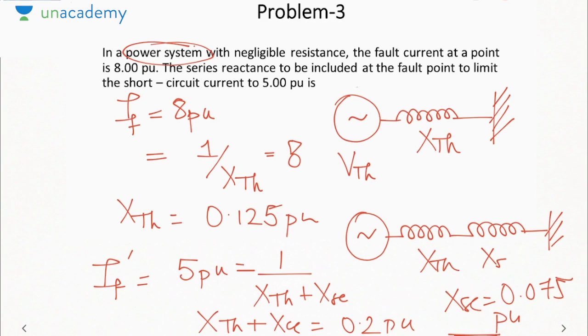Now, there is a catch here. The assumption that I have made is no load condition. How am I saying that I made this assumption? Because I took the voltage as 1 angle 0. So if the fault occurs under no load condition, then you can take the voltage directly as 1 angle 0, because no current will be flowing and there will be no voltage drop, and hence the voltage will be same as the rated voltage.